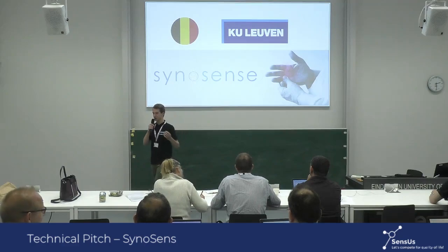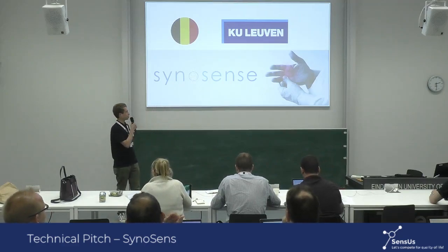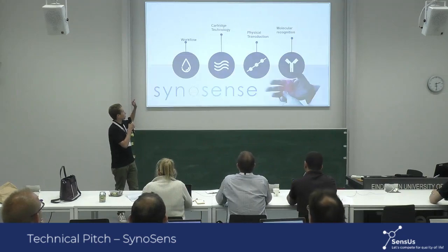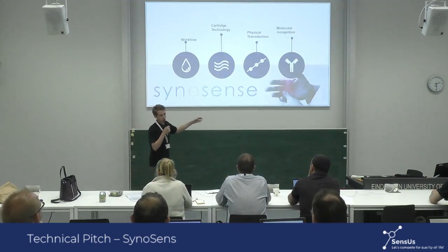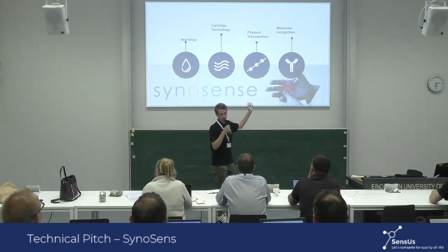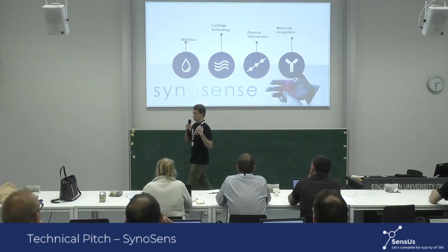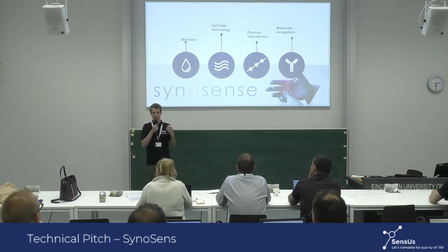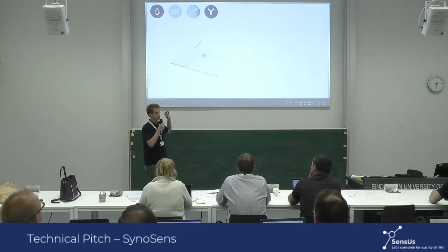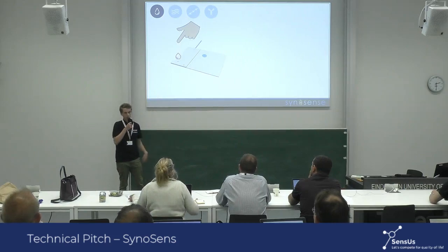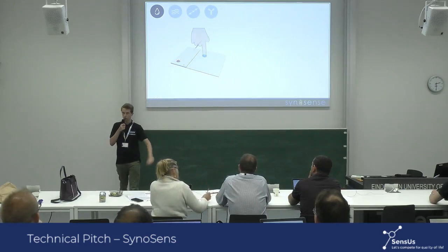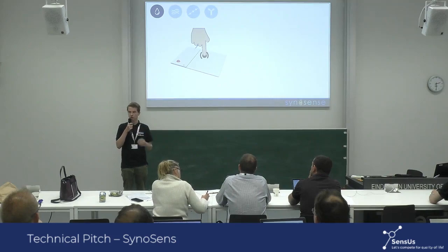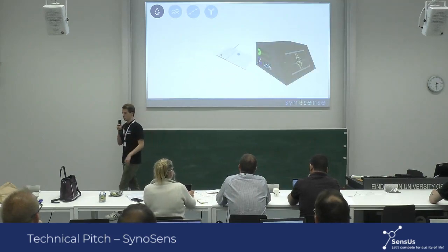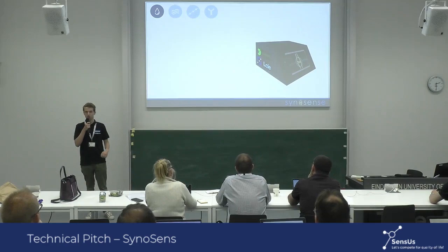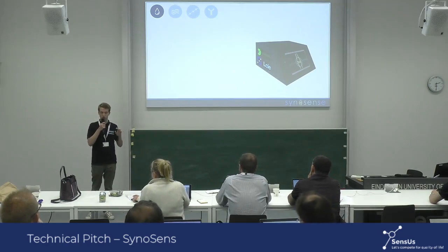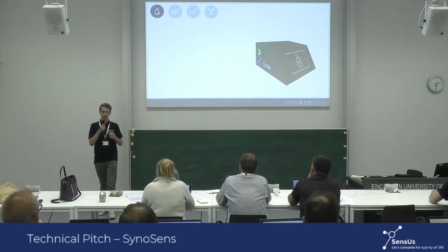In the next 4 minutes, I will walk you through the different characteristics of our sensor, starting with its workflow, its microfluidics approach, its transducer system, and we finish with the bioassay. We are very proud of the fact that our sensor does not need any sample or machine pre-treatment. You just have to put a drop of blood onto the chip, press the button, slide the whole chip into the cartridge, press measure, and the sensor will take around 200 seconds to determine the exact adalimumab concentration. The sensor is fast, accurate, but most importantly, super easy to work with.